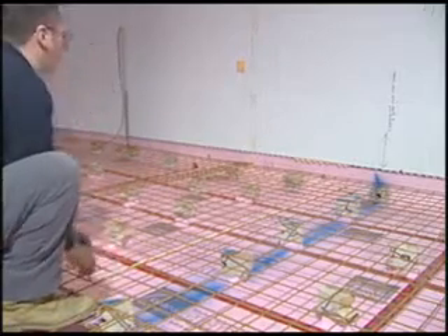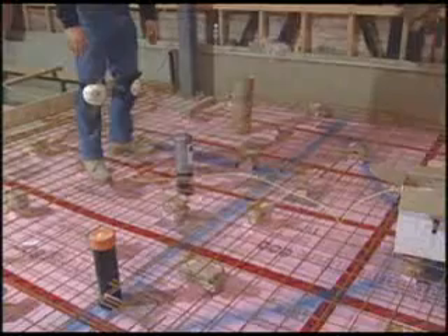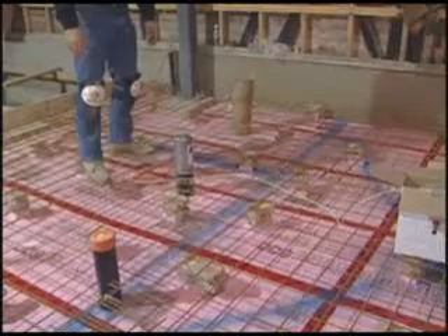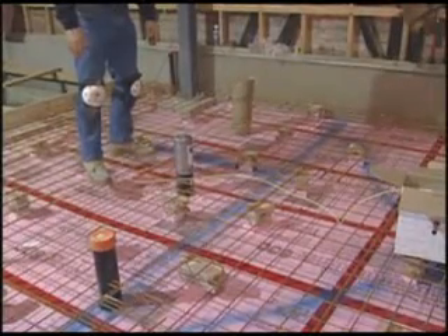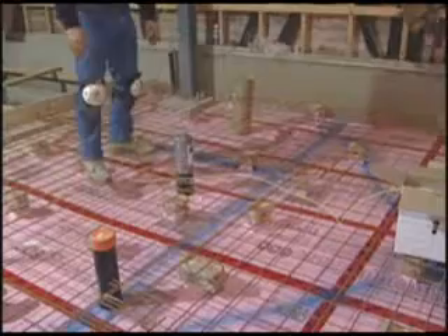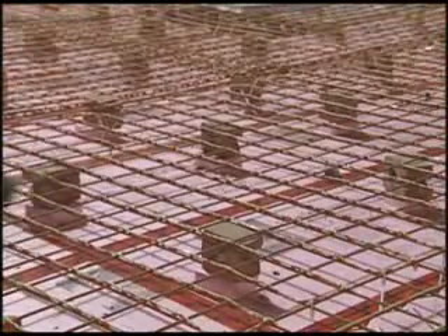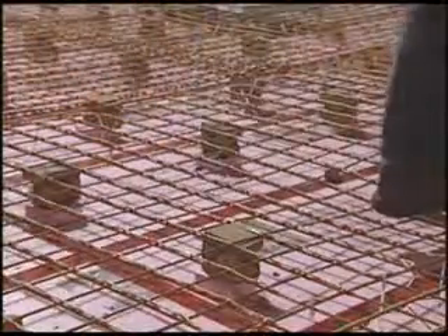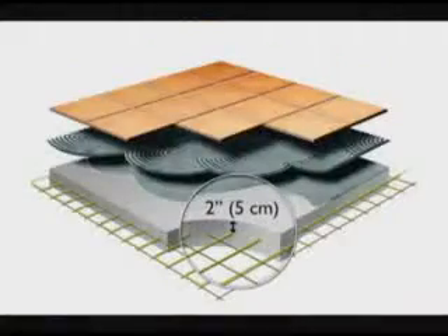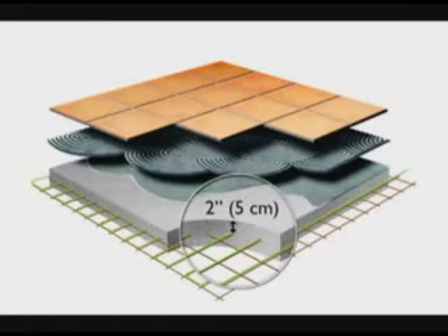under construction. First of all, prepare the surface where the reinforced concrete slab will be placed, according to local and national building codes. We recommend the use of high-density, non-compressible thermal insulation to minimize heat losses. When the steel mesh is leveled, use enough cement blocks or bricks to prevent the cables from stretching while the work proceeds. For optimal performance, the cables should be set approximately 5 centimeters or 2 inches from the intended final slab surface. Before going any further, make sure you have correctly estimated the area to be heated.